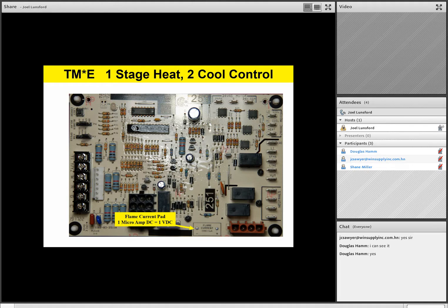So now the technician just takes the normal standard voltmeter he has in his truck or tool bag anyway, goes to DC volts, and reads voltage, which is actually translated into flame current by the control board circuitry itself. He doesn't have to have a special meter for that. All he has to do is take his voltmeter, go to DC volts, and remember, 1 volt DC is equal to 1 microamp flame current. So it's a real easy place for him to check flame current without a special meter. Are there any questions or comments on that? Again, a very nice feature that all of our Champion furnaces have on them.